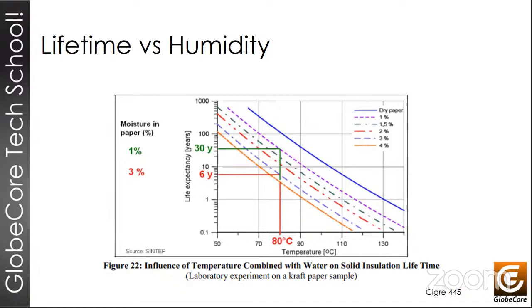But if the moisture content of the paper is 3%, so instead of 30 years, the useful life of the transformer is now 6 years with the same temperature. And that's why it's very important to keep moisture out of the equipment. We can do that because it's a variable that we can constantly measure and correct accordingly. So we see that if we increase the humidity a lot, we'll have much higher loss of useful life. So you can see that it can drop as low as 4 to 5 years. Once again, it's extremely important to keep humidity inside the transformer low. Next slide, please.